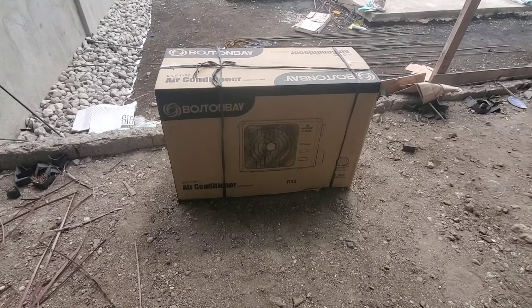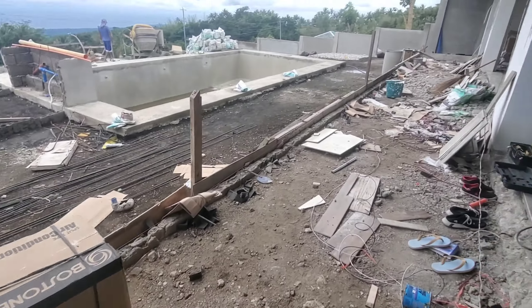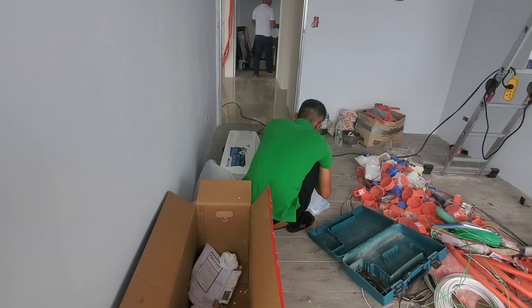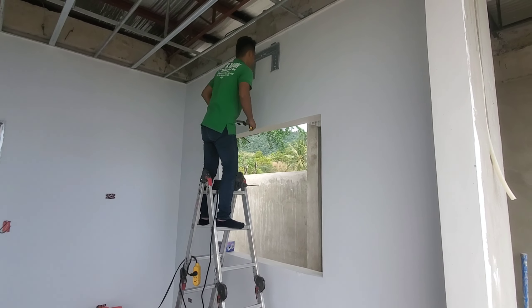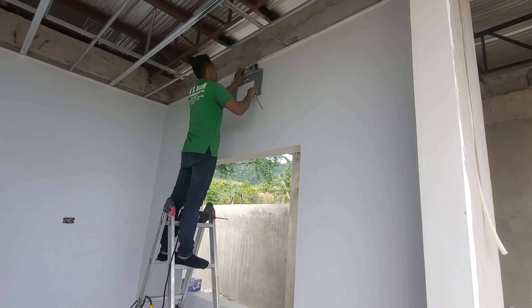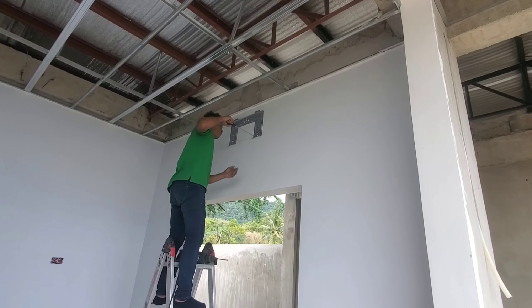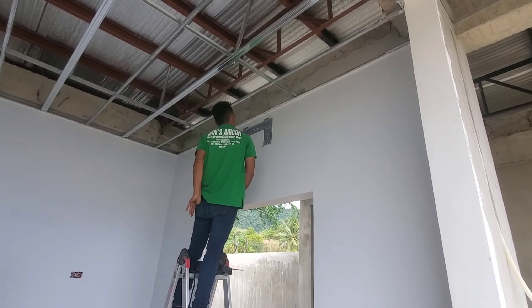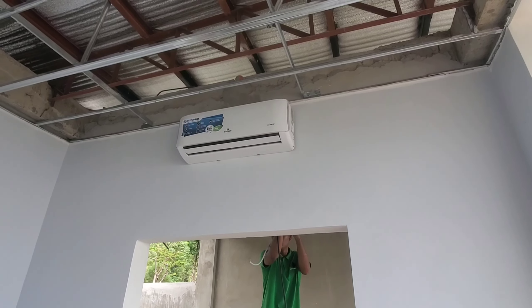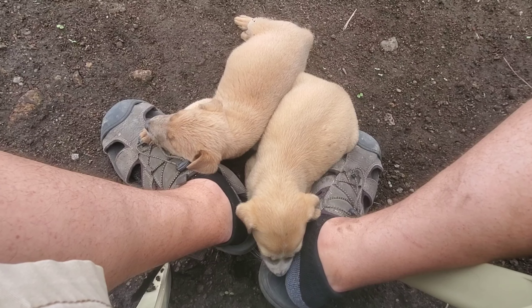The guys told me that Boston Bay product is a sister company of Carrier, so the internal components are the same as Carrier — that's good news. For the two spare bedrooms, the units are 1.5 horsepower. The first step is putting in the bracket for the inside air con unit — they drilled four holes into the wall, put in cement screws, and have a level up there making sure it's level. The first 1.5 inside unit has been installed — centered to the window with a minimum clearance of three inches to the ceiling.